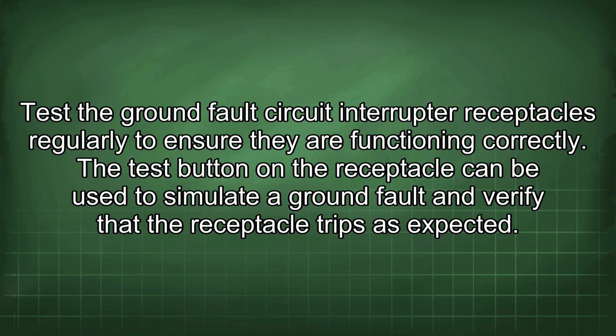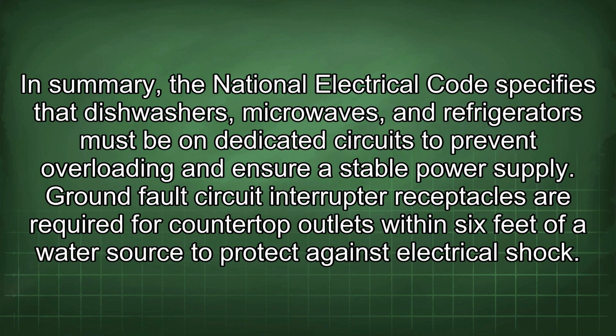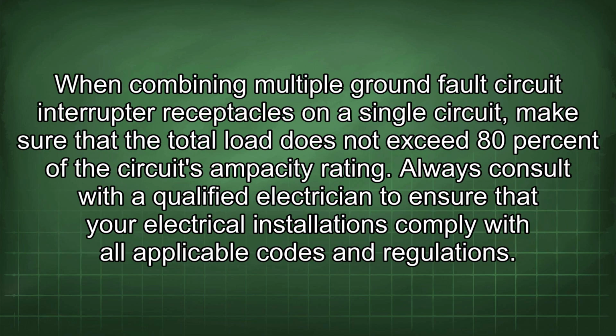as expected. In summary, the National Electrical Code specifies that dishwashers, microwaves, and refrigerators must be on dedicated circuits to prevent overloading and ensure a stable power supply. Ground fault circuit interrupter receptacles are required for countertop outlets within 6 feet of a water source to protect against electrical shock. When combining multiple ground fault circuit interrupter receptacles on a single circuit, make sure that the total load does not exceed 80% of the circuit's ampacity rating.